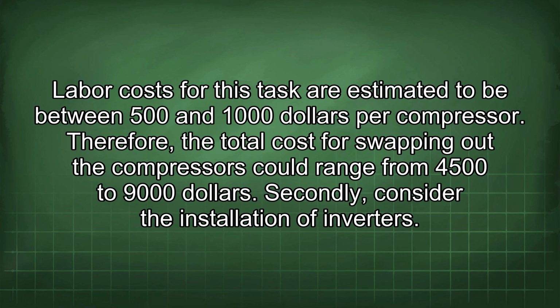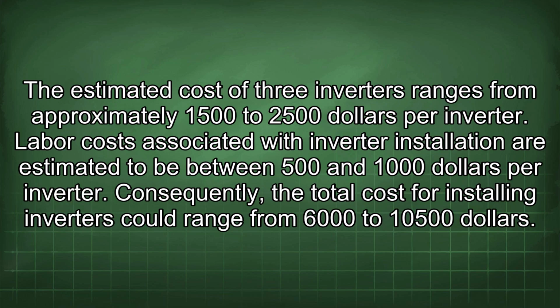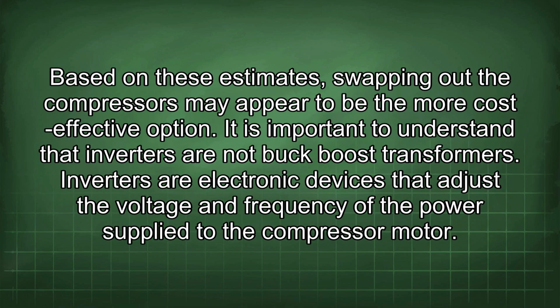Secondly, consider the installation of inverters. The estimated cost of 3 inverters ranges from approximately $1,500 to $2,500 per inverter. Labor costs associated with inverter installation are estimated to be between $500 and $1,000 per inverter. Consequently, the total cost for installing inverters could range from $6,000 to $10,500. Based on these estimates, swapping out the compressors may appear to be the more cost-effective option.